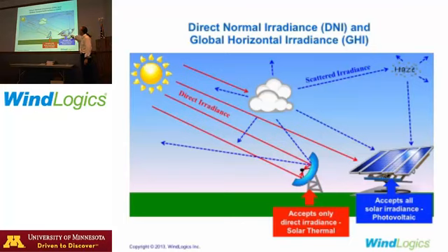The other thing that's interesting is that PV also picks up reflection off of clouds. So as a big cloud bank is coming toward a PV site, just before the cloud gets to you, you'll actually see a slight uptick in power output before the cloud shadow hits you, because the sun is reflecting off the cloud down to the panel, right? So a lot of things to think about with this. We can actually tell the difference even on which side of Phoenix a project is on. We'll see a different solar irradiance value because people water their lawns in the city. That increases the humidity on one side of the city versus the other. That will be detectable in terms of the amount of haze you have out there and how the direct beam is affected. So it's tricky.